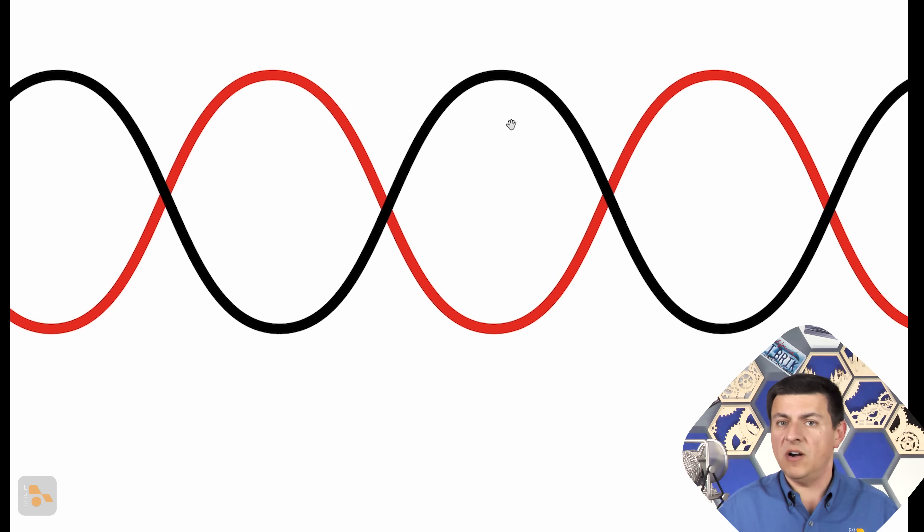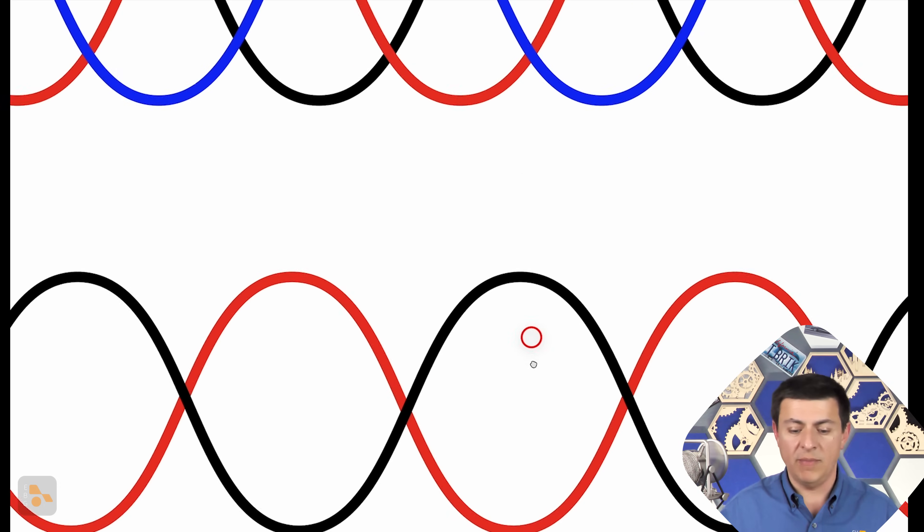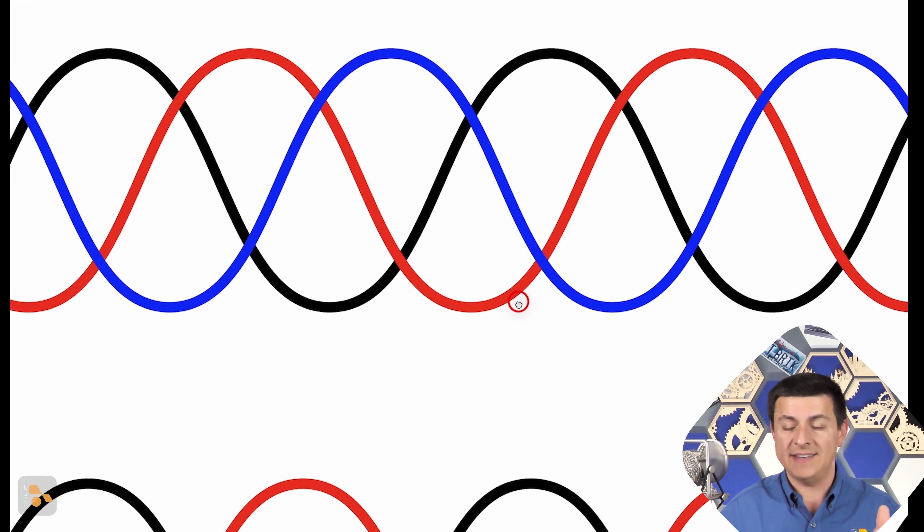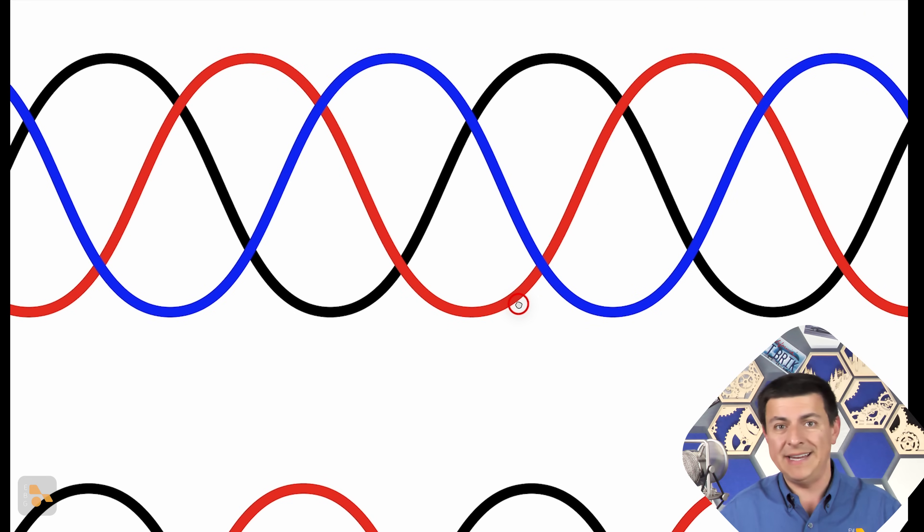And the three-phase part is critical. From that transformer, it then goes up to this disconnect box, and then it goes into this 208 volt three-phase breaker panel. And then all the loads come off of there. I don't want to get too far off in the weeds here, but this is what the waveform of single-phase power looks like. This is what the waveform of three-phase power looks like. And yes, it is single-phase still, even though it looks like that, and it kind of looks like the sort of DNA strands right in front of you. And that's because the different phasors of single-split-phase power don't relate to a rotating magnetic electric field. That's why it's not two-phase power. That's why it's single-phase.